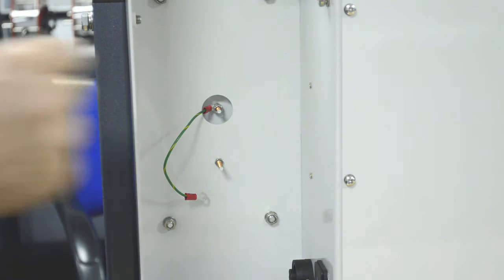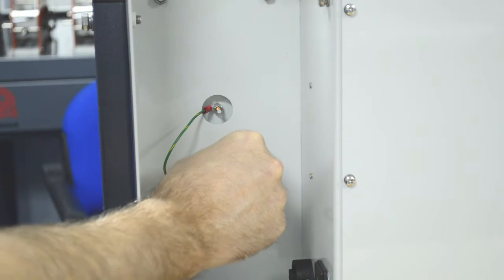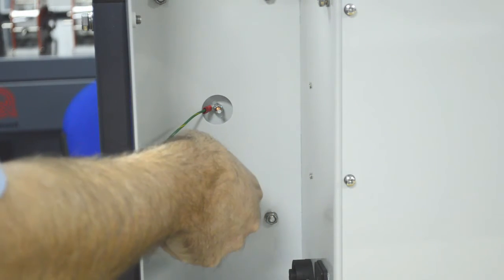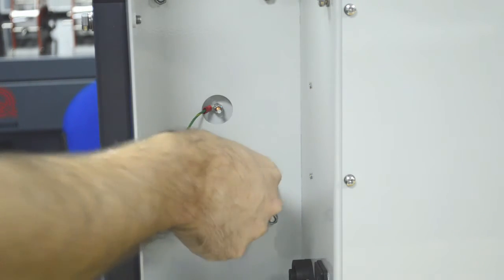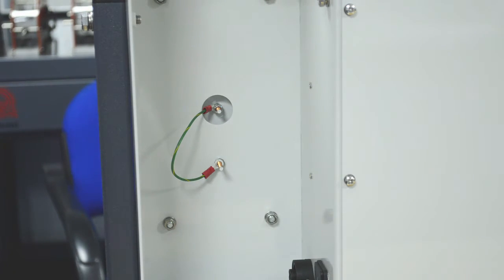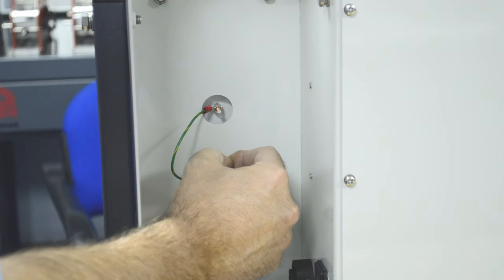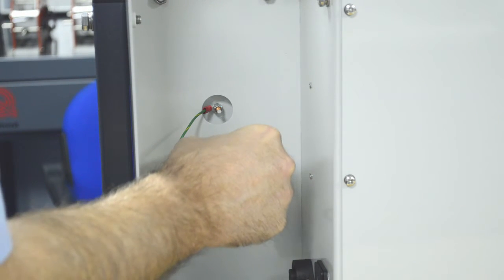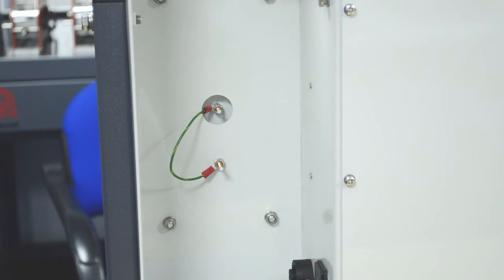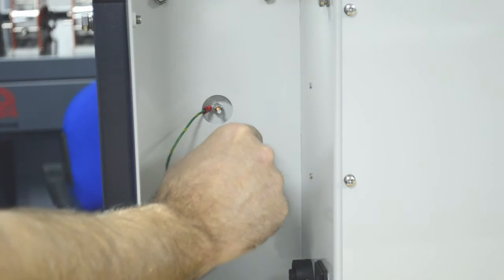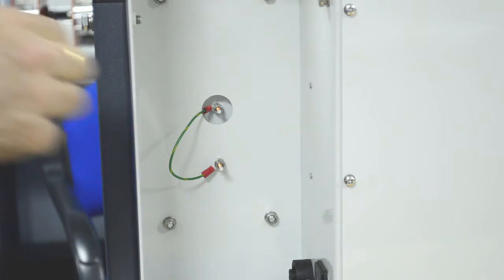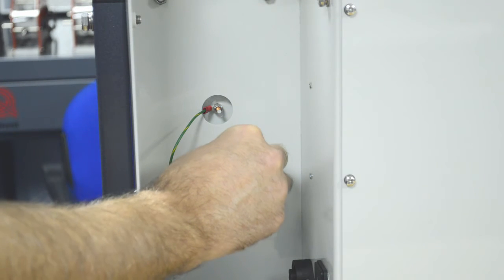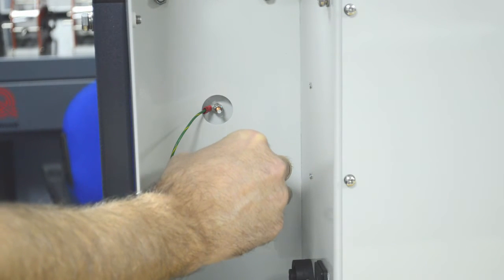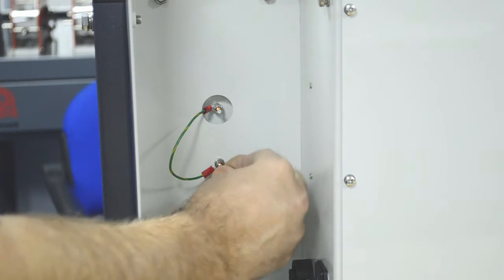At the rear of the duct, connect the short earth cable from the duct to its stud on the main base unit. Use an M7 socket with ratchet or a nut runner to tighten the nuts. Do not over tighten. Hold the green earth cable gently to prevent it from turning whilst doing up the nut.